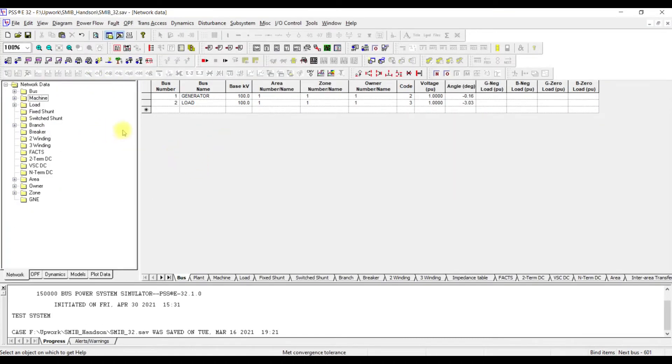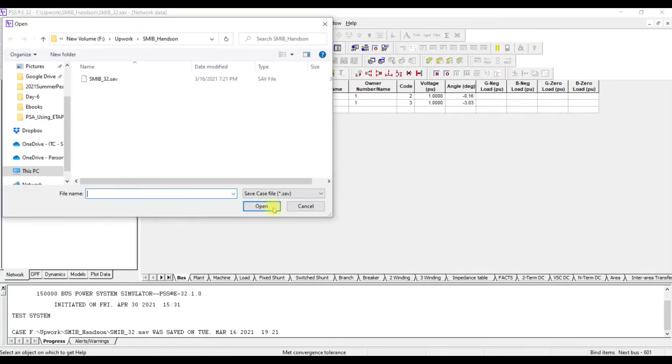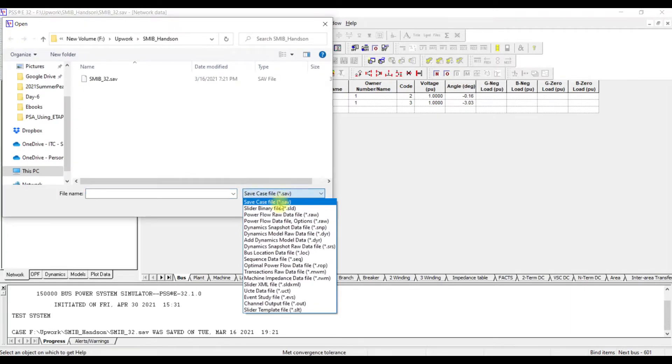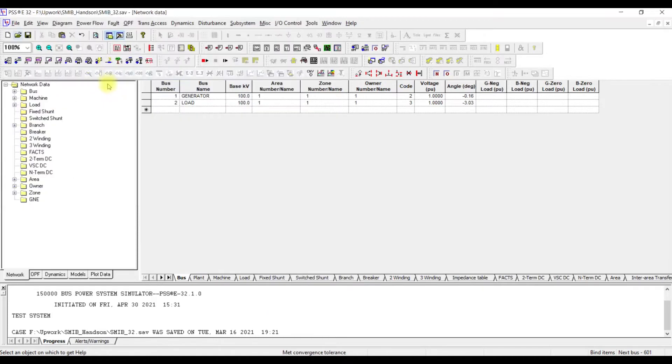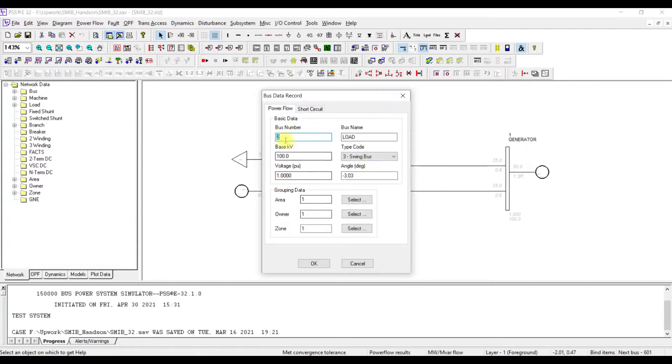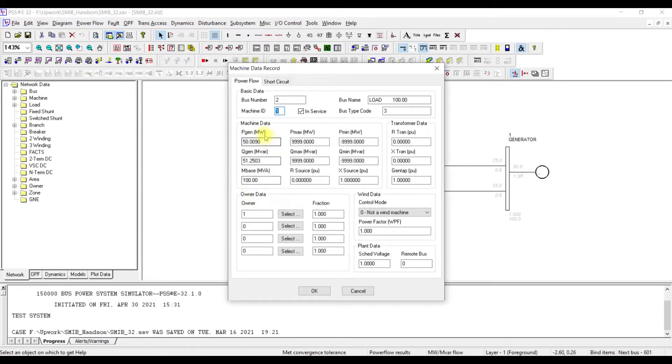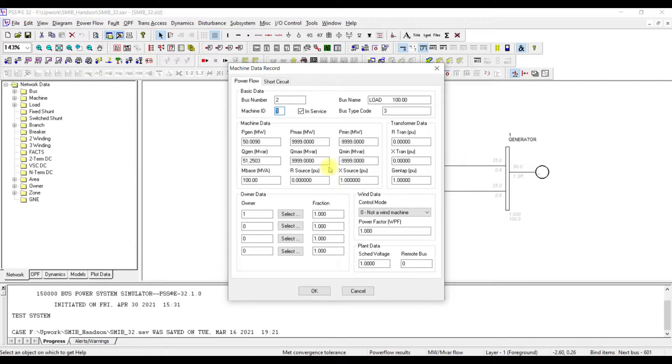Here, if you see this case is a very simple case consisting of only two buses. To further understand this case, let us open the SLD file. If you have the SLD file it is okay, if you do not you can create an SLD file. For SLD file, again open from this drop-down list, select slider binary file and select SLD. If you want to create this case, what is this case? Here we have this swing bus known as bus number 2. At this bus, we have a generator with PGEN of 50 MW and we haven't provided any Qmax and Qmin value.